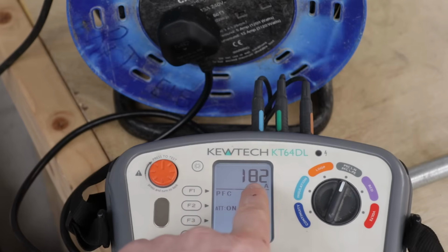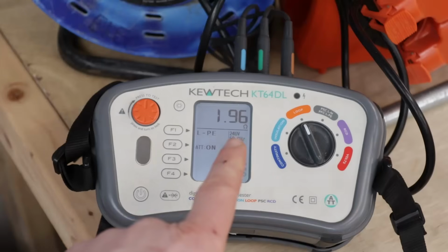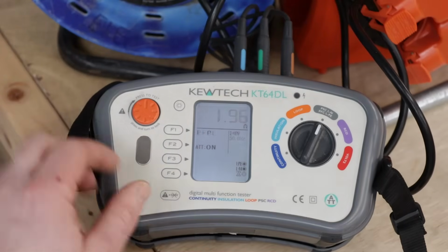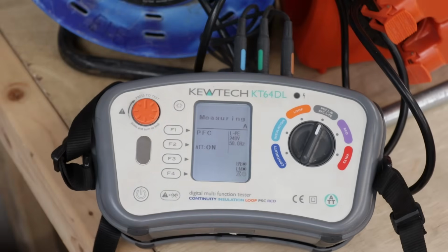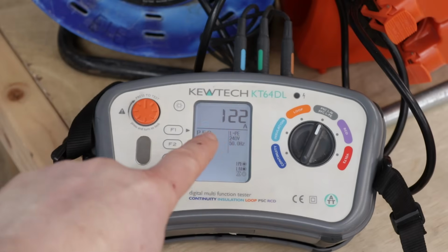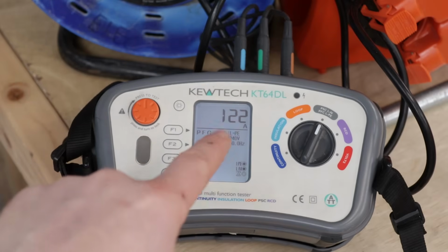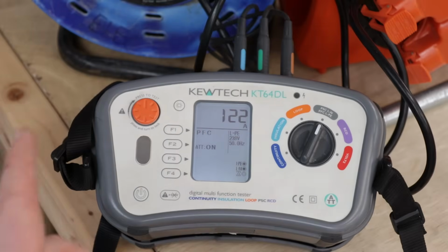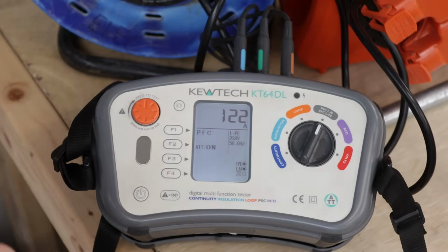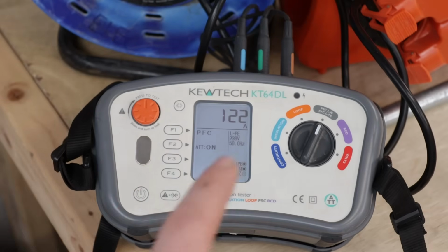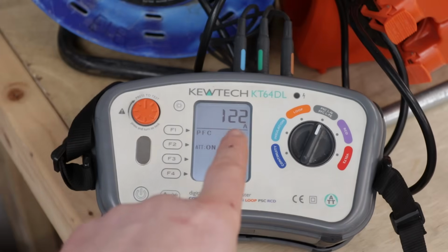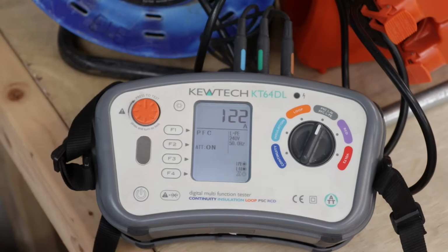So let's just add the second extension lead now and see what happens. There you go. We've jumped up to 1.96 ohms now. So if I go to the short circuit current, let's have a look at what we're going to measure there. Okay, so we're down to 122 amps now, so we're getting very close to the limit of this breaker, what it needs to blow it out. So you can see the danger. Now, again, I've oversized my socket cable, so if I had put in 2.5s for my socket circuit, which would be technically fine for the load carrying capacity, but not for the distance, this is where it's important. If that was a 2.5 cable, I would be down to 100 amps or below on a short circuit.